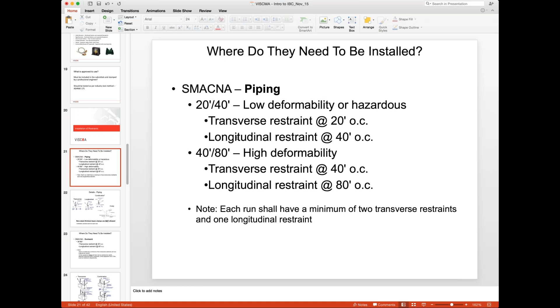Here, from a schematic point of view, is the type of detail you'll see on a submittal or on MEP drawings, broken up fairly simply. A transverse, just as it says, has two cables or two rigid, structurally designed restraint elements set perpendicular to the run of the pipe. It's shown in 3D and also in plan view, where you just put a bar across the piping run, calling it out as a transverse, or sometimes a two-way.